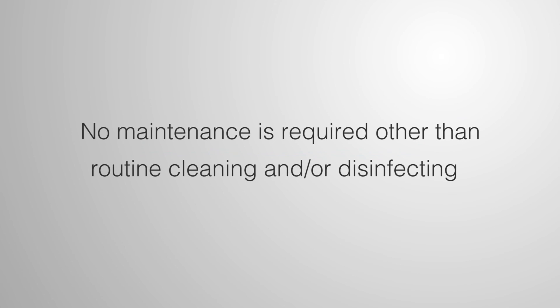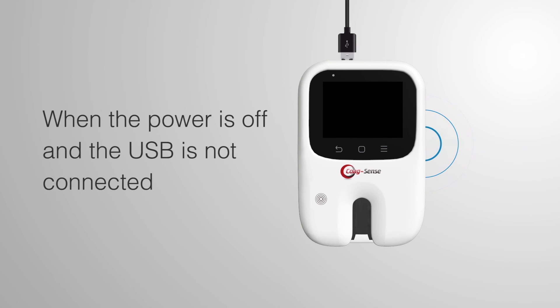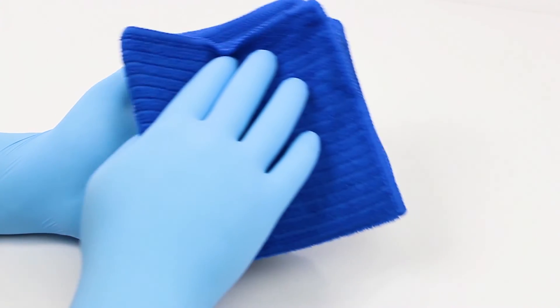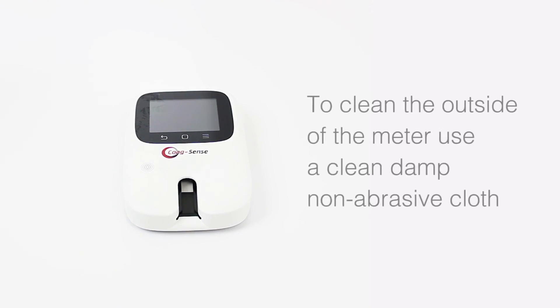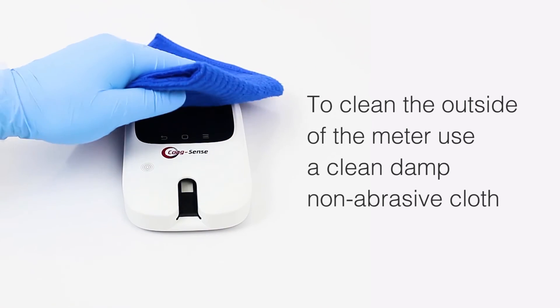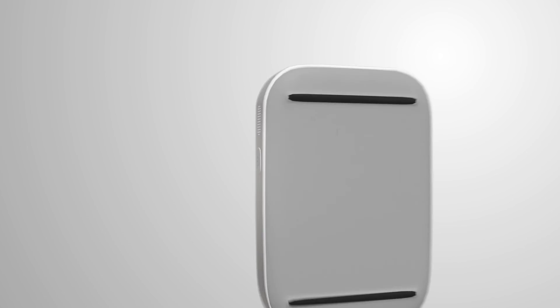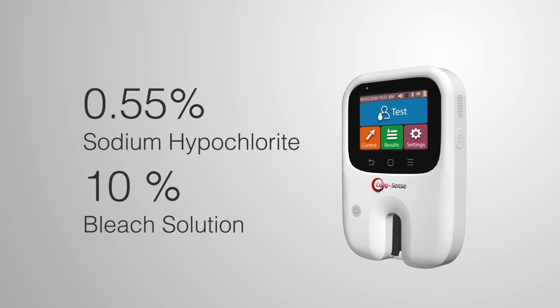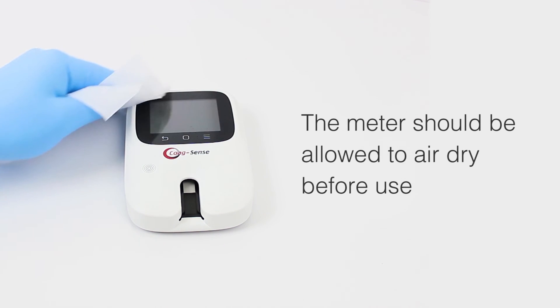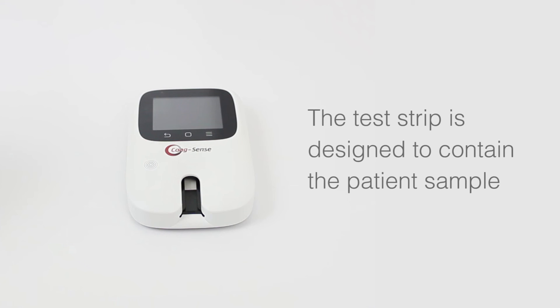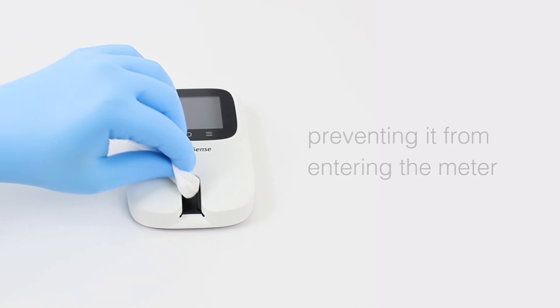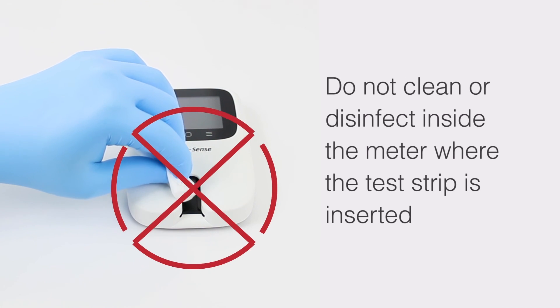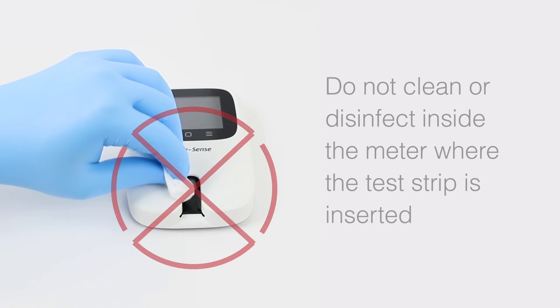No maintenance is required other than routine cleaning and/or disinfecting. When the power is off and the USB cable is not connected, the meter housing can be cleaned and disinfected. To clean the outside of the meter, use a clean, damp, non-abrasive cloth. The meter can be disinfected using any germicidal wipes that have 0.55% sodium hypochlorite or 10% bleach solution with a 1-minute contact time. The meter should be allowed to air dry before use. Do not clean or disinfect inside the meter where the test strip is inserted, as cleaning this area should be avoided.